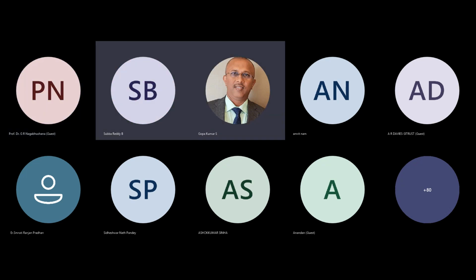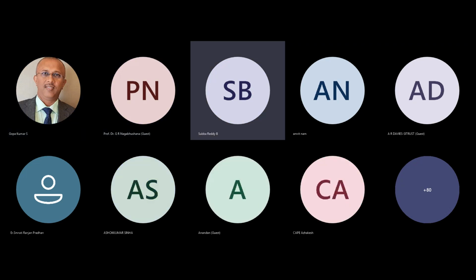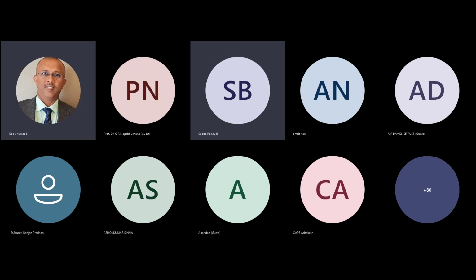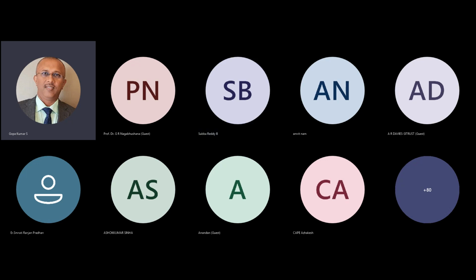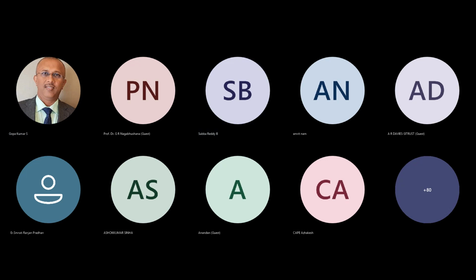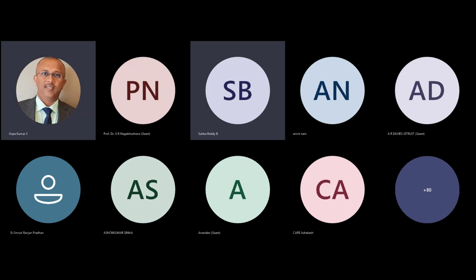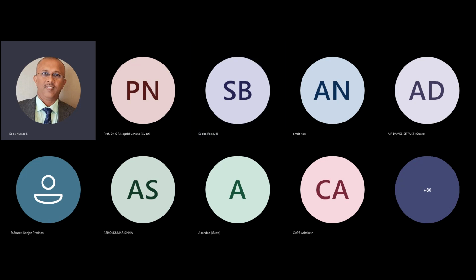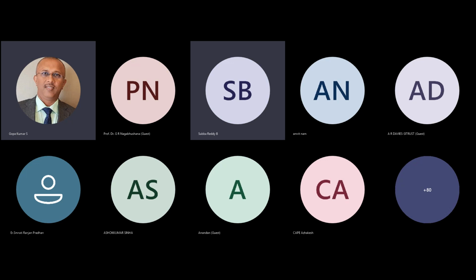Sir, with your permission, can I answer this question, sir? Yeah, sure. See, you are talking about the low voltage installations, I hope, electronics in the building, not related to the high voltage application. Am I correct? Yeah. Actually, in the system earlier, we were thinking you connect everything to the earth electrode in soil. This was never included or written in any of the standards. The standards always considered your earth a protective conductor, which is a metallic busbar. You connect everything to the metallic busbar. That was the concept from the beginning until today in the standards.